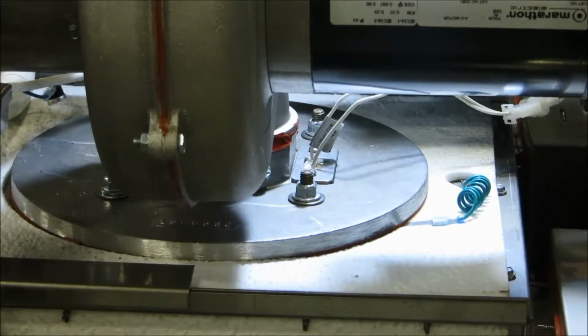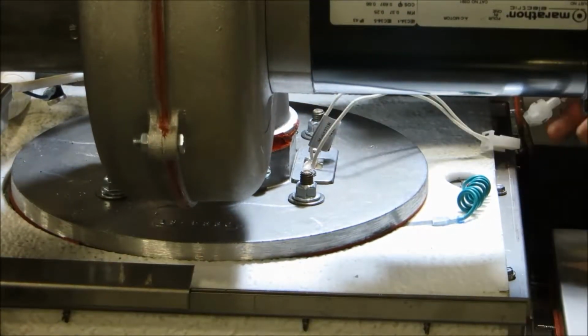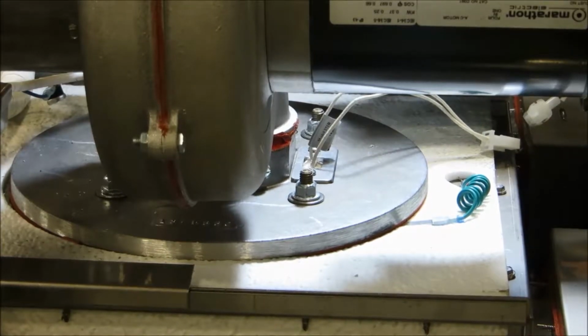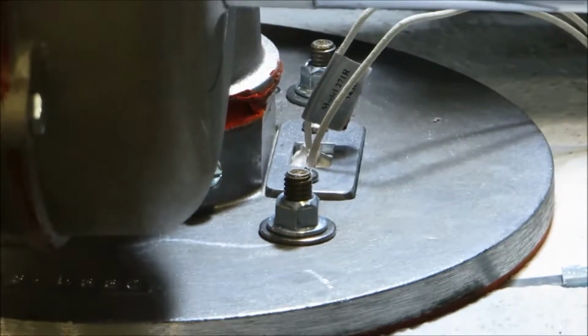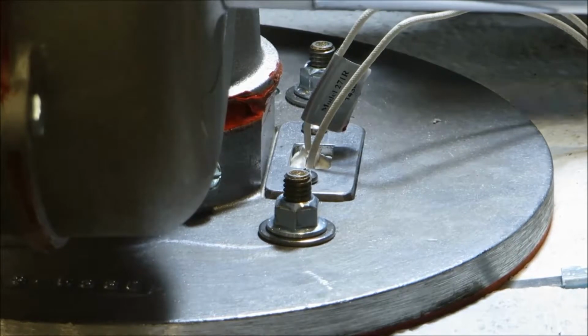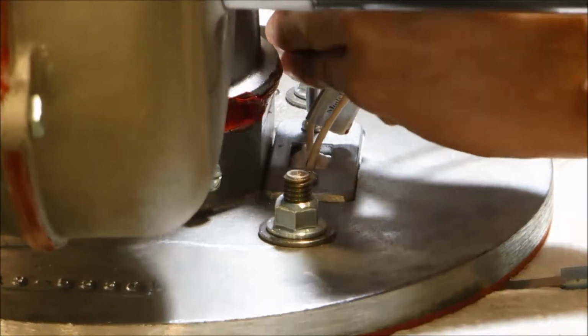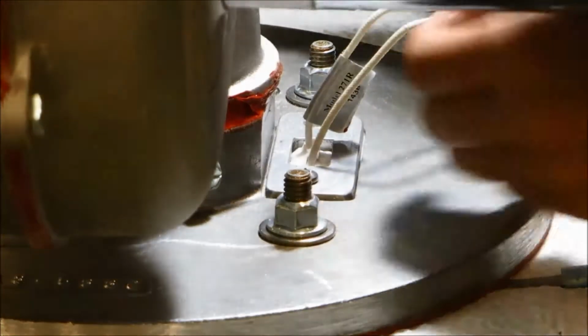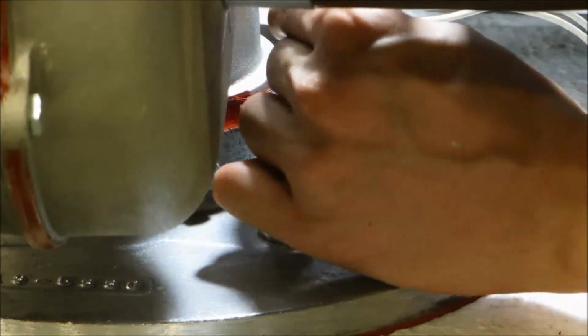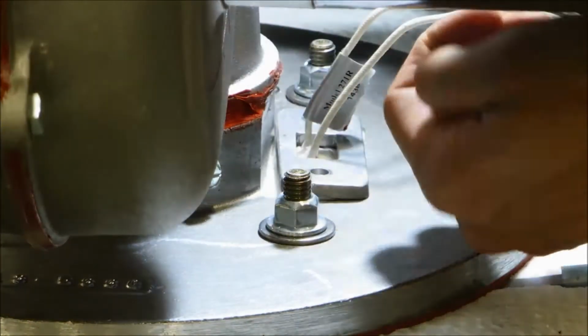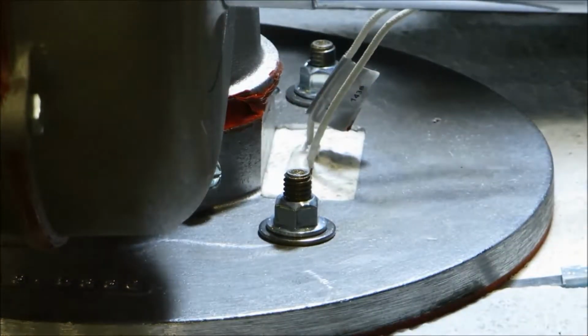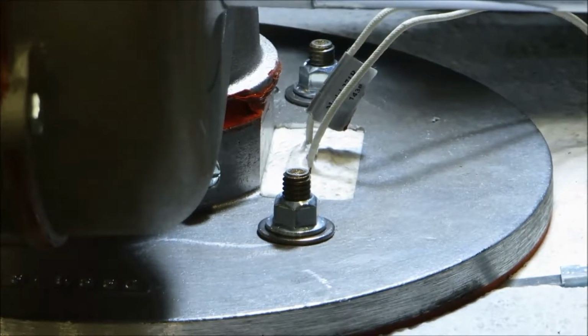To remove the hot surface igniter, first unplug the igniter from the harness. Then remove two Robertson screws holding the igniter in place, and then slide the aluminum bracket off of the wires. Carefully remove the igniter by gently pulling it vertically upwards. Do not angle or wiggle the igniter, as that will break the tip of the igniter.